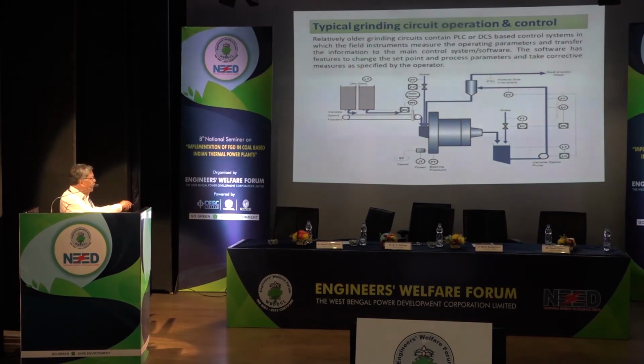So in the ball mill, you actually have here by conveyor belt the fresh feed. And this is what we call recirculating load. That means total feed to ball mill consists of fresh feed and recirculating load. Recirculating load can be up to 100%; in case of limestone, it can be 150 to 200%, even a little more, because limestone is soft. If the material is hard, for example iron ore, it can be 300%, 350%. Even there are instances of 400%. No material gets pulverized in one single pass. So they have to come back.